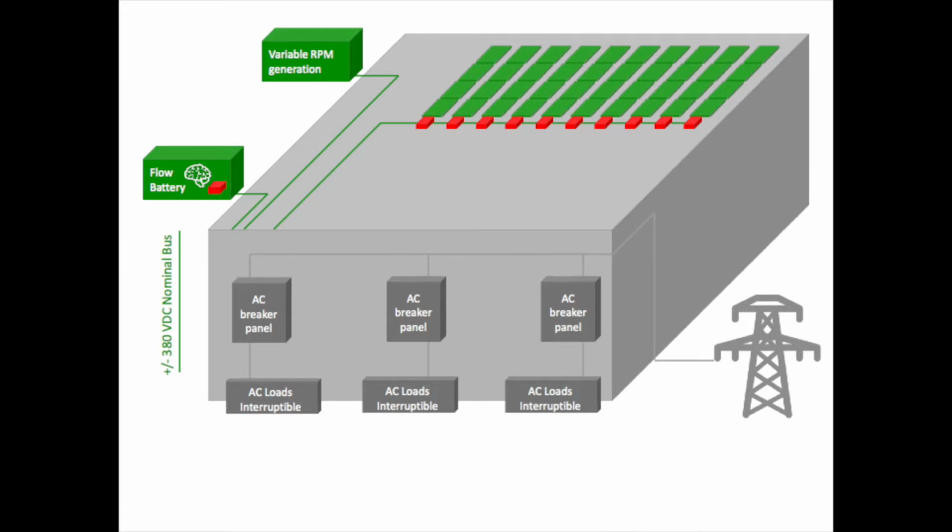The ARDA battery DC-DC converter contains a distributed virtual microgrid controller that manages power and energy, maintains DC bus voltage, and uses the DC bus to communicate with sources and loads. This eliminates the requirement for a separate wired or wireless network.